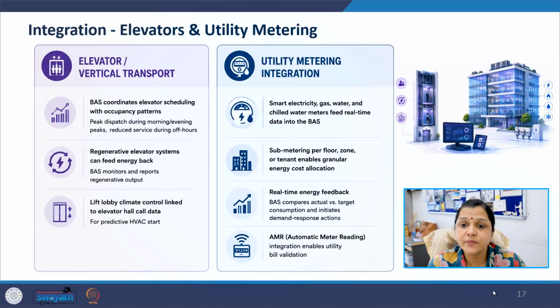So the next integration will be at the level of elevators and utility metering. BAS integration also extends to elevator and utility metering systems, as elevator schedules may be coordinated with occupancy patterns. Peak hour operation and off-hours operation can be managed differently. Some modern elevators also generate regenerative energy, which can be monitored by the BAS. The BAS may even predict HVAC demand in lift lobbies using elevator hall call data. This hall call data is very important.